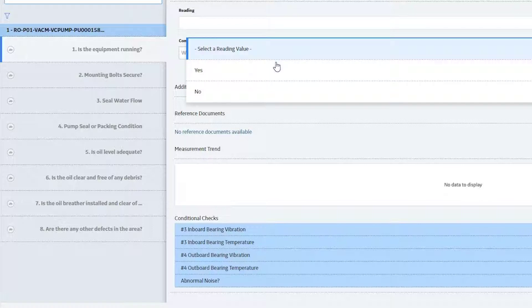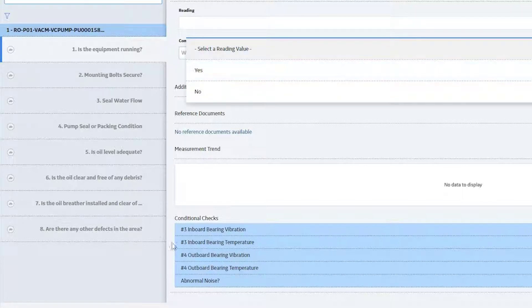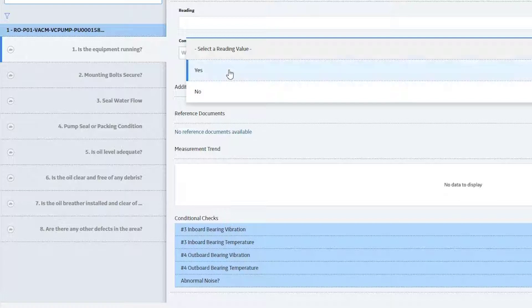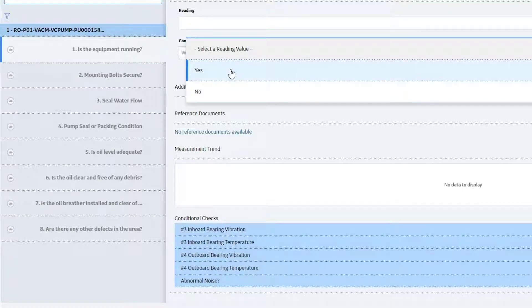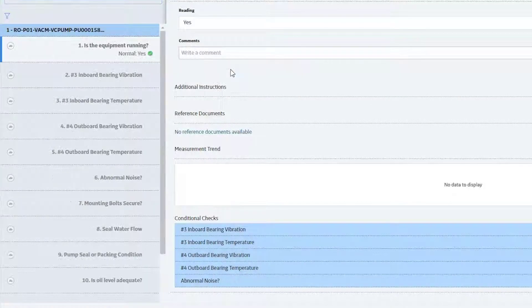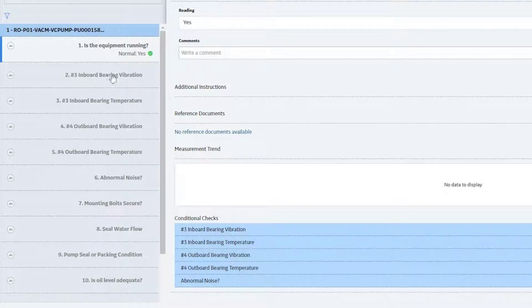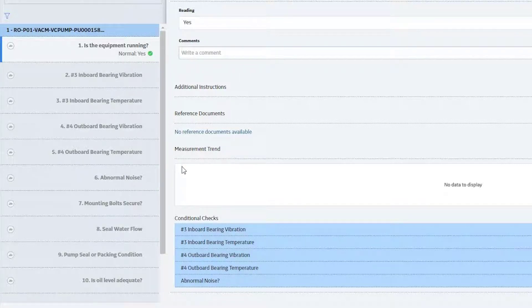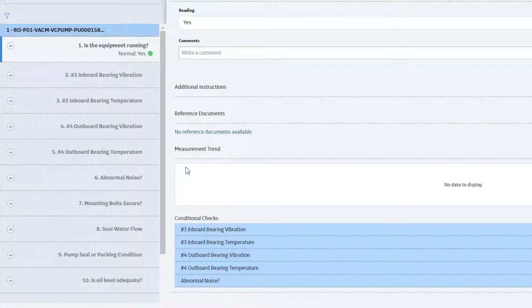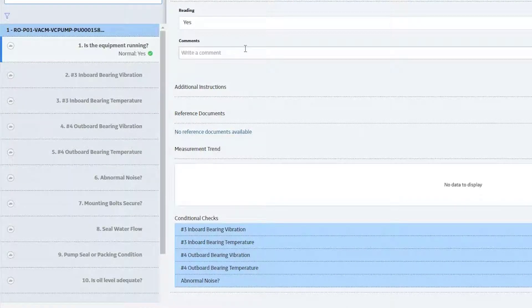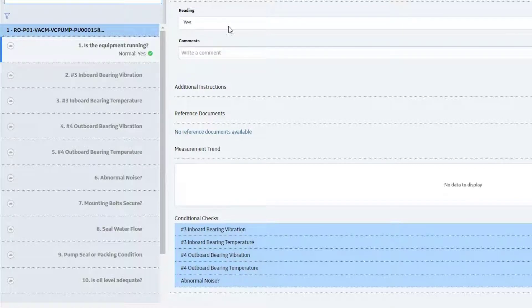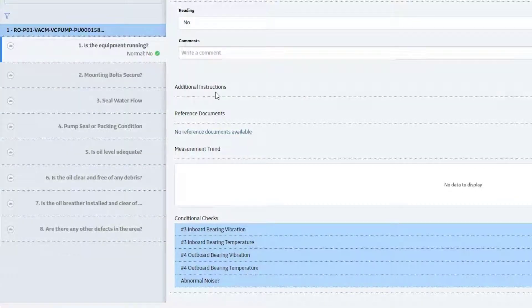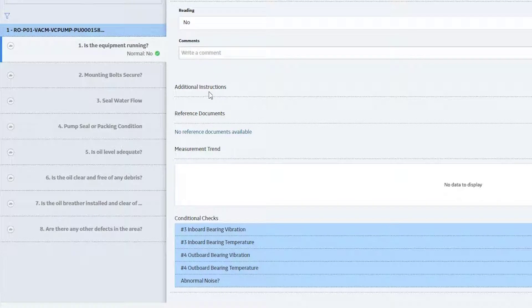Now this happens to be a conditional check, and the way you know that is if you look down here, it says conditional checks and it's got five additional questions. So if I select yes, notice that these five questions pop in here. That's because I can only do those checks when the equipment's running. If the equipment's not running, there's no point in me seeing those because I can't collect that information.